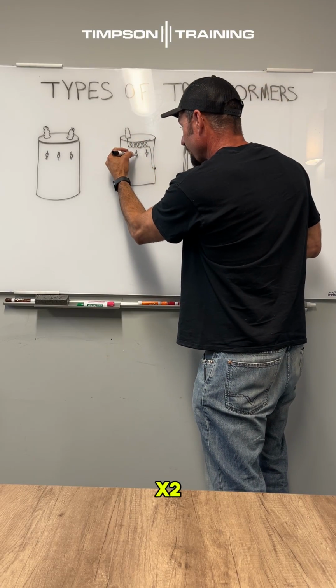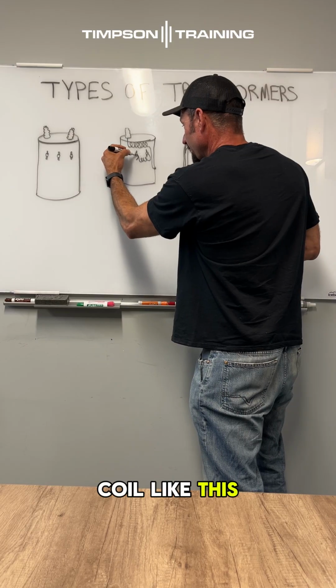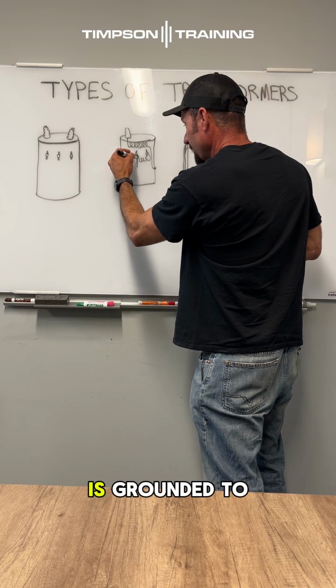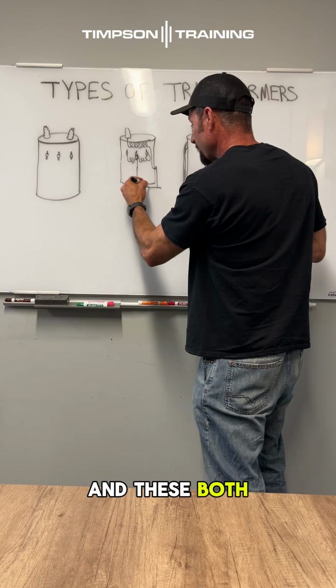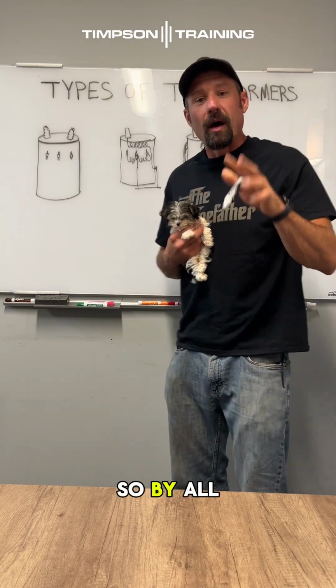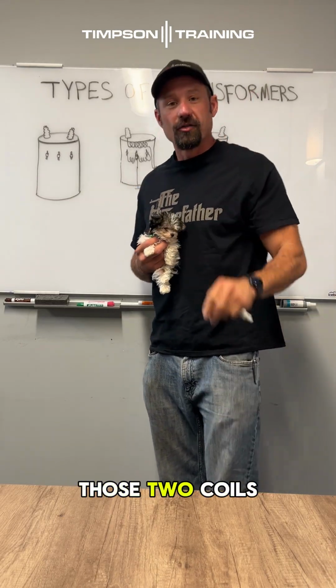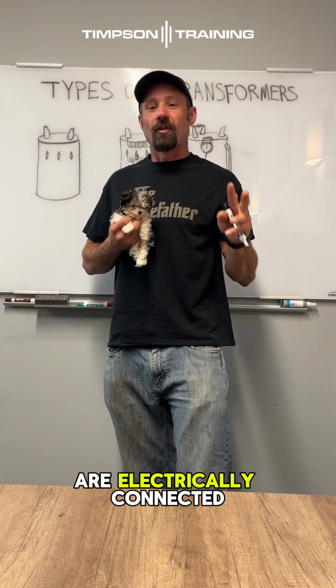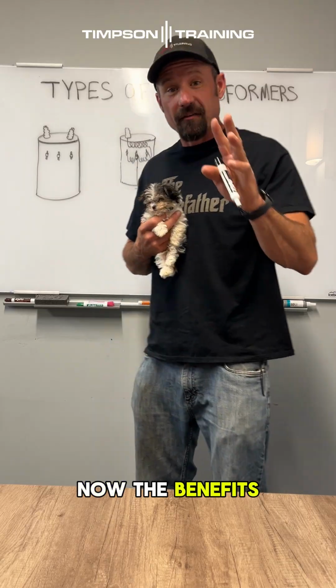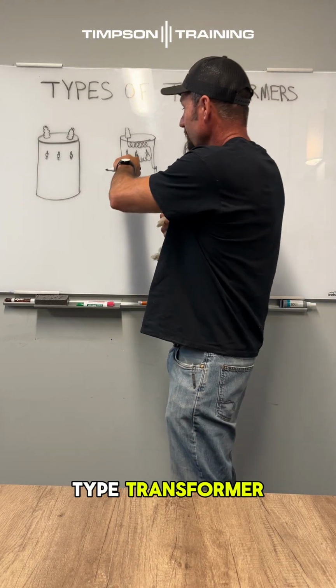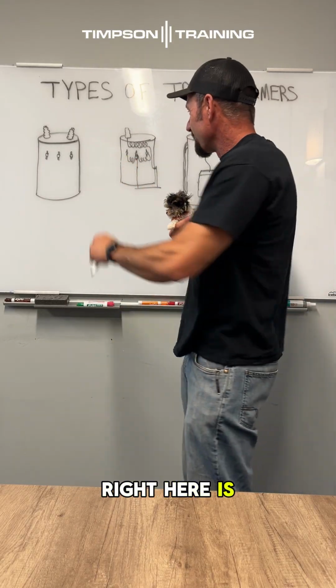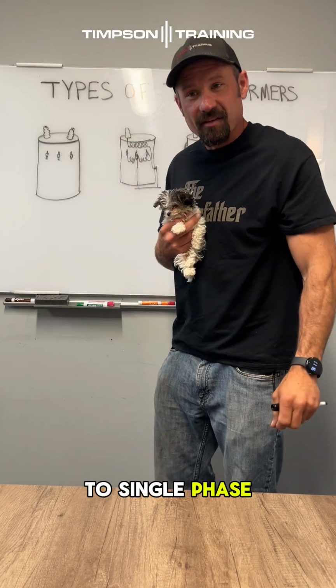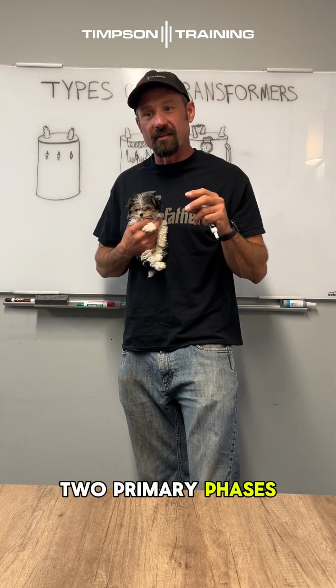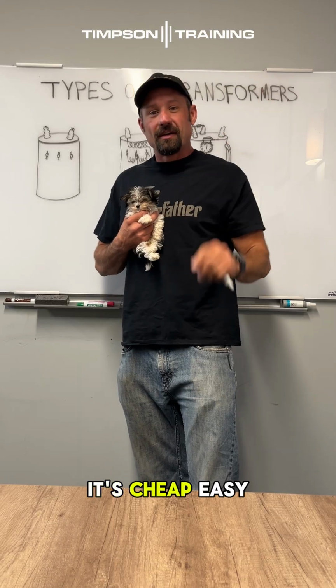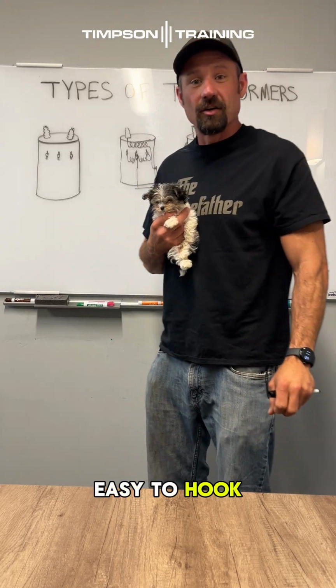And then our X2, you have your coil like this, and this also is grounded to the case, and these both get grounded to the neutral. So by all intents and purposes, those two coils in that transformer are electrically connected through the ground. Now, the benefits of this conventional type transformer right here is that we can hook it up to single phase. You don't need two primary phases. It's cheap, easy to make, easy to hook up.